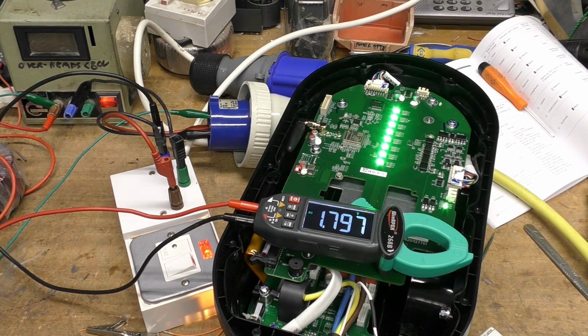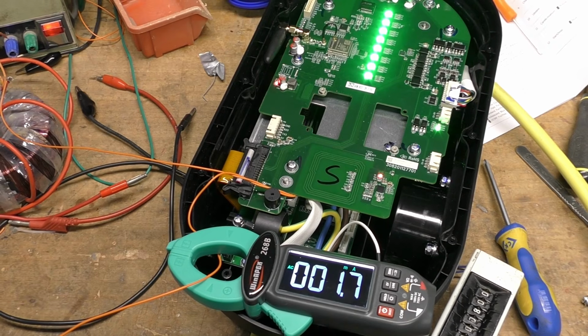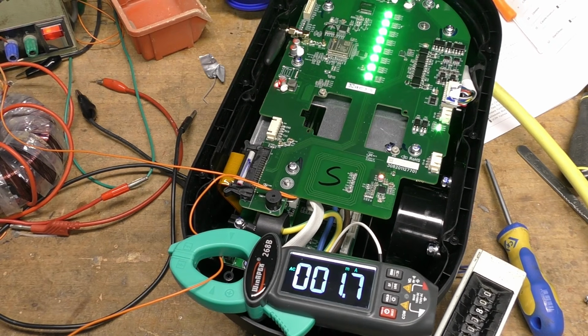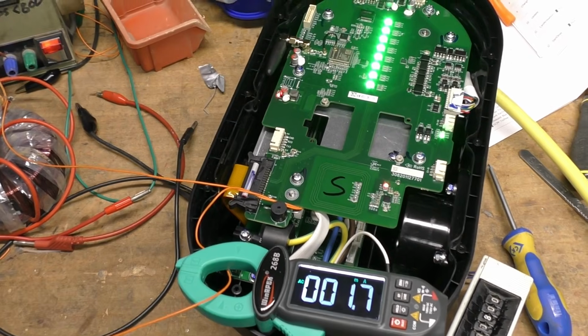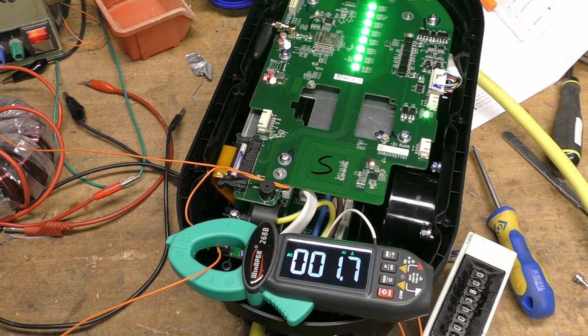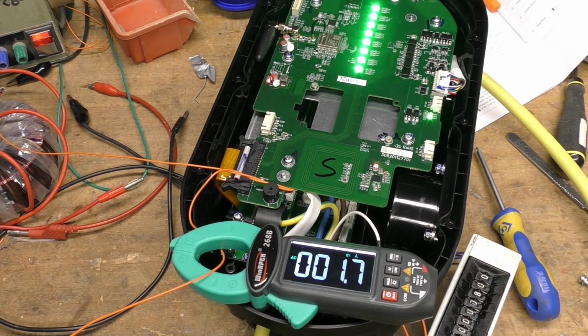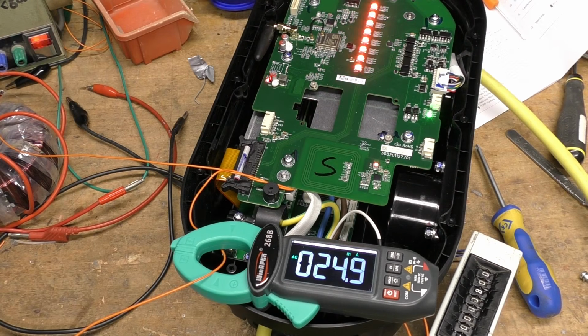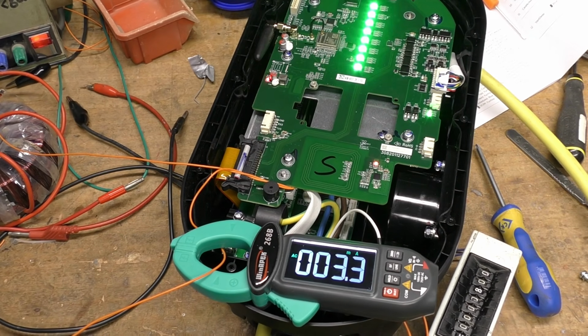Yeah, and that also self-resets. So it looks like the only thing that actively latches is when you actually get excessive current through the earth connection, which would generally be a fairly bad situation. So I think it's not unreasonable that it should latch off in that state. Okay, let's check the main residual current detection and see where that trips. I've just put a turn around the transformer so I can inject a current into it. It's tripping at 25 milliamps, that's with no car connected.